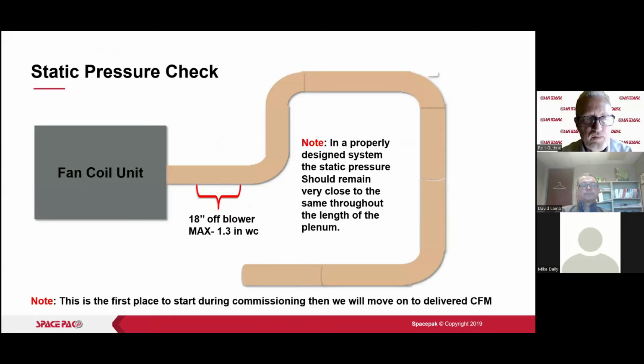All right, static pressure check. Where you would check that static pressure would be 18 inches off the blower. It says max 1.3. You could be at 1.5. In a properly designed system, the static pressure is going to remain the same throughout the system. If it's not, then we've got some problems, probably old duct, too small of a duct, or an inadequate number of outlets.